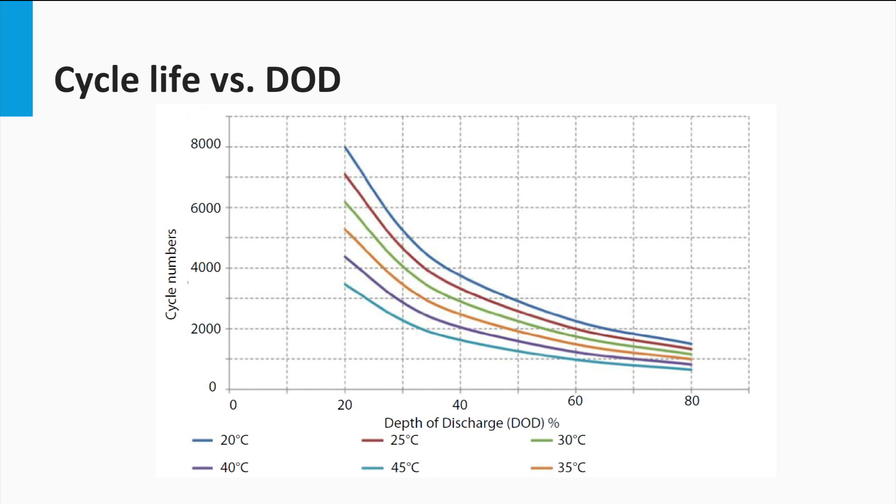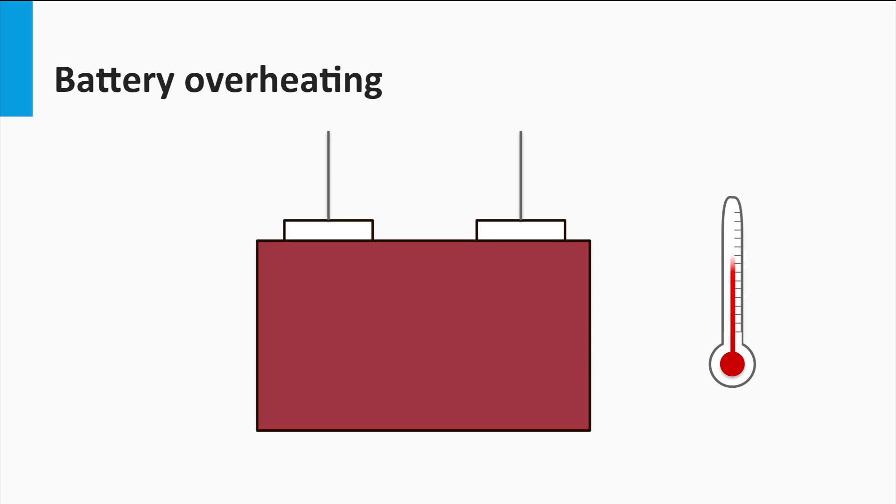However, such a higher cycle life would also mean that those additional cycles you gain can only help you for a smaller depth of discharge. Thus, it could be said that the battery will last longer if the average DOD could be reduced over its normal operation. Also, battery overheating should be strictly controlled. Overheating could occur due to overcharging and subsequent overvoltage of the lead-acid battery. We will learn more about voltage and charge control of the battery in the next video.